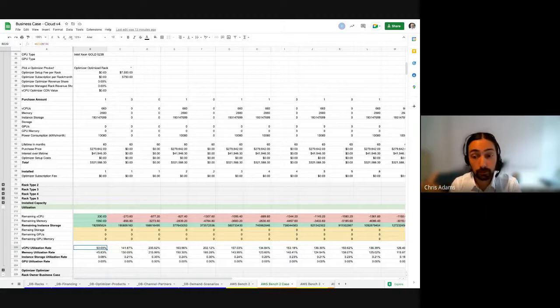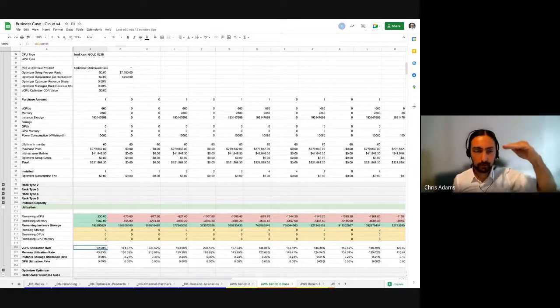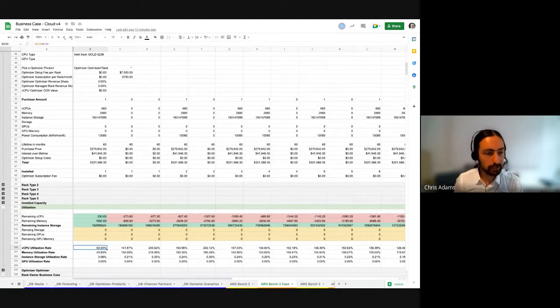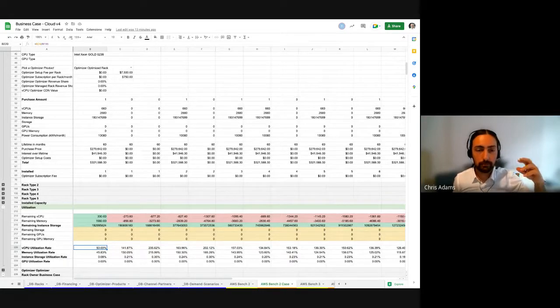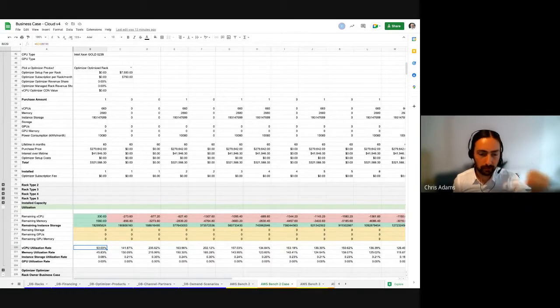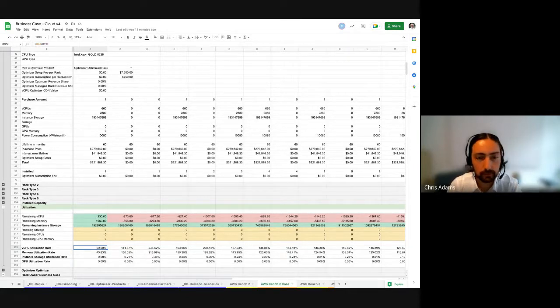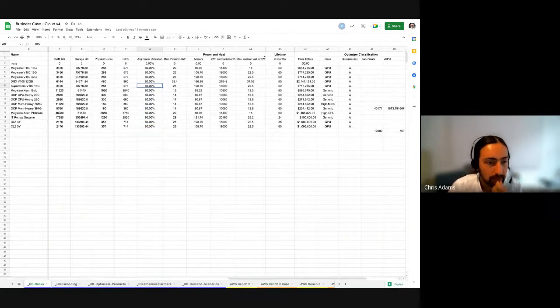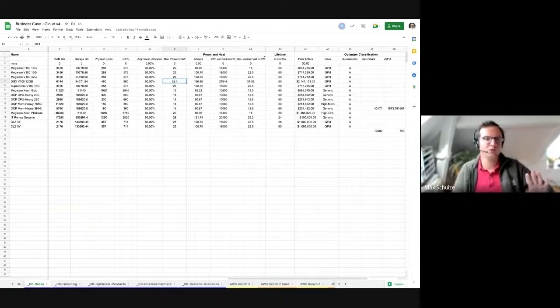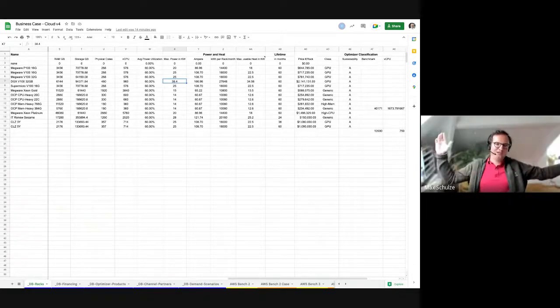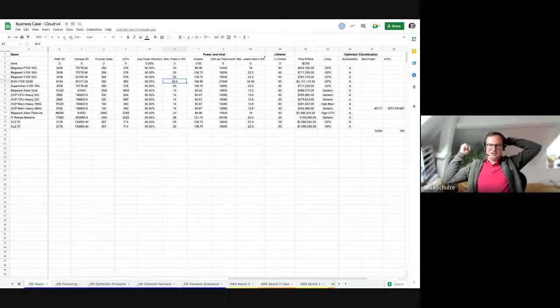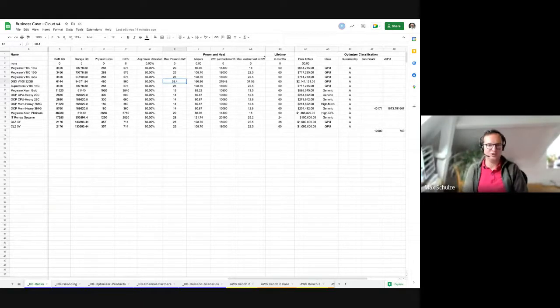When talking about higher and lower up the stack, we touch on energy costs but don't model the grid infrastructure costs implied by a rack drawing something like 40 kilowatts — and when you put 10 racks together that becomes significant power draw. These numbers in the database represent the whole rack's rated power from manufacturer specifications multiplied by how many servers fit in a rack. Actual trustworthy numbers. You get up to 40 kilowatts, and once you're at 40–50 racks you're looking at a megawatt of draw automatically.